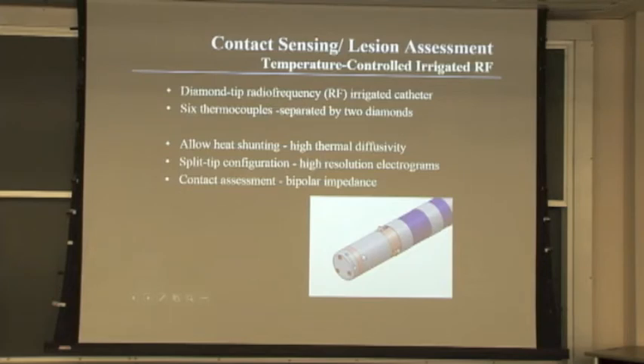Well, this particular catheter is interesting because, as I showed you, it has these 3 thermocouples as well as thermocouples on the back end. It also has a split tip, so you can see very small electrograms. And the tip is, instead of made of platinum, it's mainly made of industrial grade diamond, which apparently has extremely high thermodiffusivity, so the heat equilibrates very quickly. Why am I telling you all this? Well, what this ultimately ends up is a catheter where you deliver energy based on the tissue temperature, at least the surface temperature. So you end up delivering energy very efficiently into the tissue.